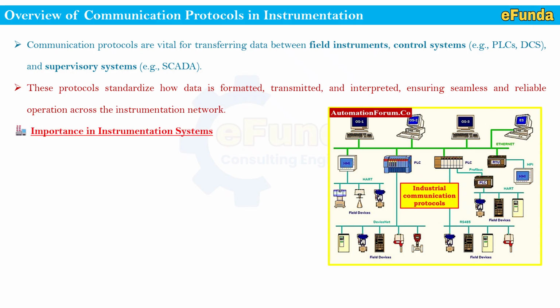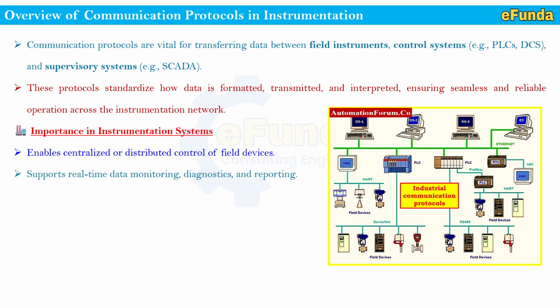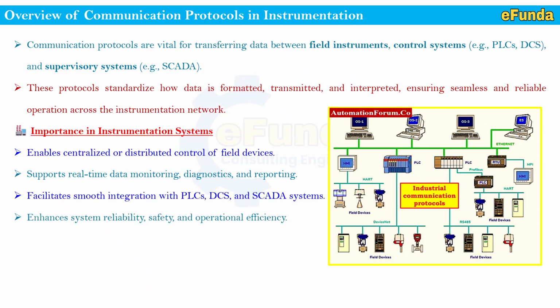Importance in instrumentation system. First, it enables centralized or distributed control of field devices through the communication protocol. Communication protocol supports real-time data monitoring, diagnostics, and reporting, facilitates smooth integration with the PLCs, DCS, and SCADA systems, and enhances reliability, safety, and operational efficiency. Because of using communication protocol, it helps field devices talk freely with the control system in terms of their communication language, that is a transfer of data in the form of machine language, that always ensures system reliability and operational efficiency.